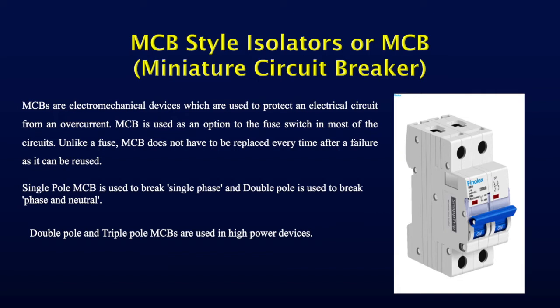Different types of MCBs are available: single pole, double pole and triple pole. In domestic single-phase connection, there is one phase and one neutral. If only the phase wire is connected to the MCB, it is a single pole. If both phase and neutral are controlled by the MCB, it is double pole. For three-phase connections, a triple pole MCB is used.